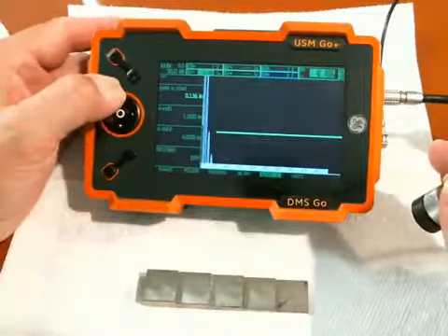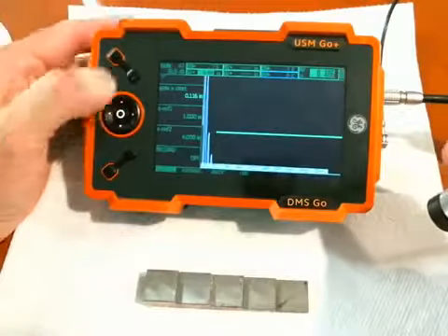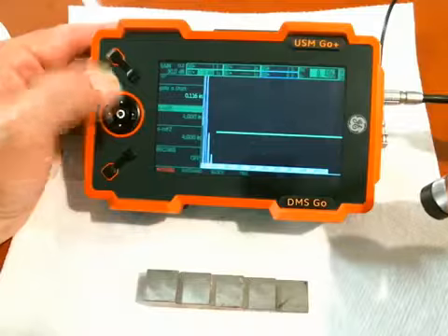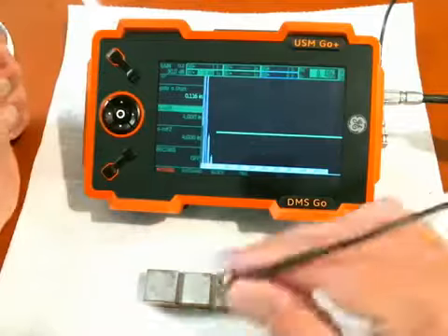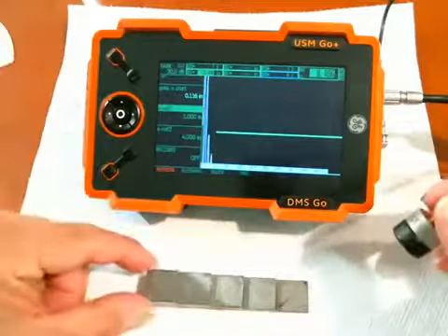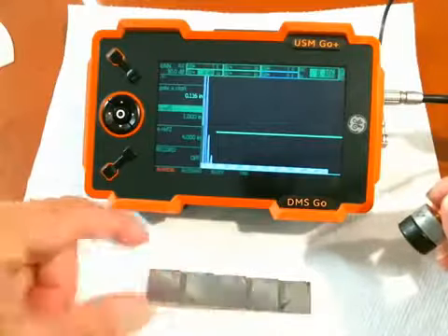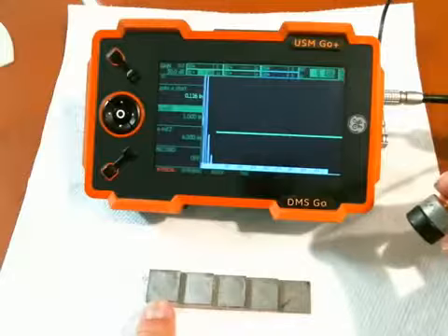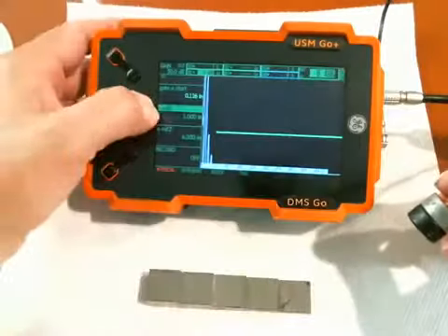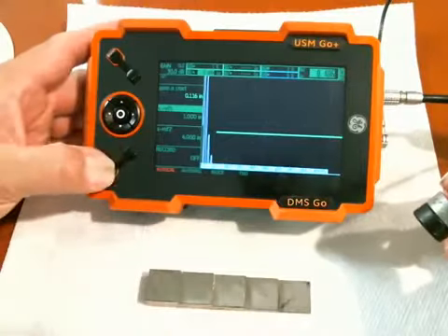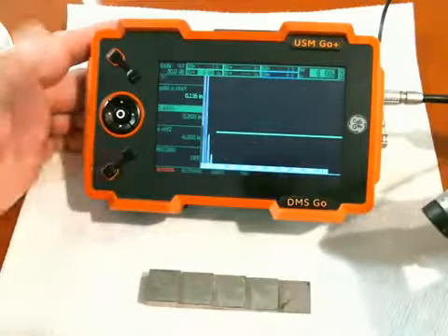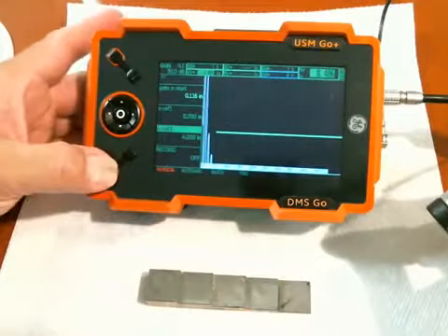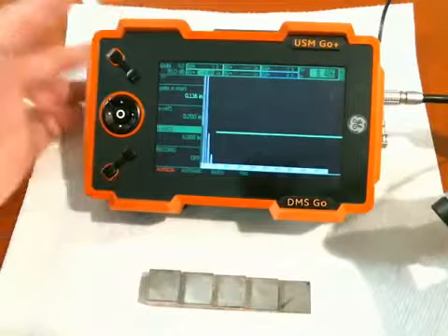If I go up on AutoCal, it's going to ask me for 2 reference thickness points. We're going to do a 2-point thickness calibration. We're going to give it 2 reference points. So I have my block here. I'm going to tell it that my thin reference is 0.2 inch, my thick reference is 0.5 inch. SREF1 is my thin, so I'll adjust that to be 0.2. SREF2 is my thick. I'm going to adjust that to 0.5.